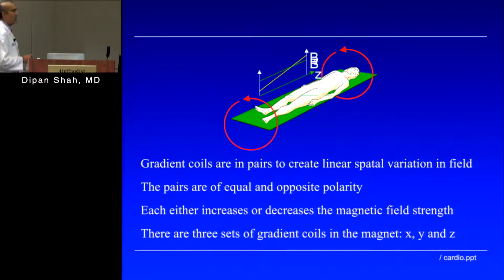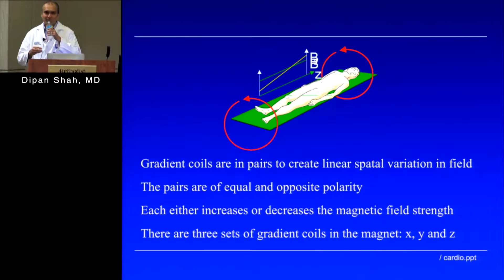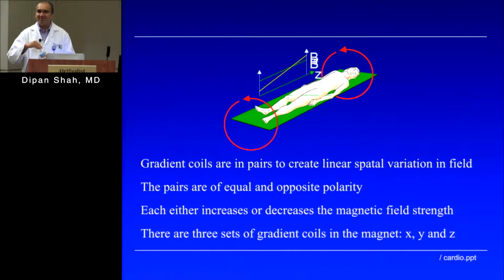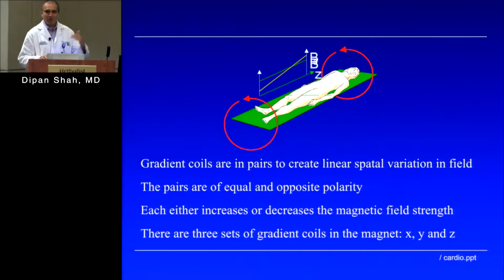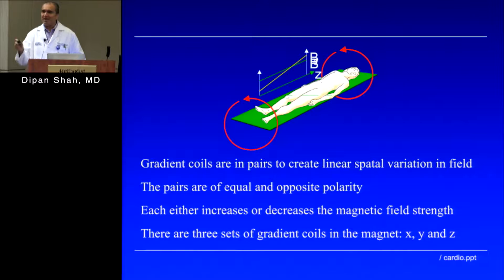What is the purpose of the gradients? Gradients cause a local alteration to the magnetic field. The static magnetic field stays at 1.5 tesla, but I can cause a slight distortion to the magnetic field by applying a gradient — for example, in the head-to-foot direction. The net effect is that the magnetic field at the head will be slightly different than at the center versus at the feet. We're talking about very minor changes: maybe 1.5001 tesla at the head and 1.4999 tesla at the feet.